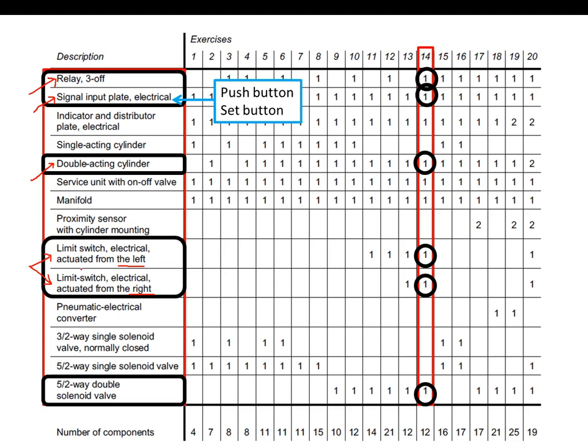We also need to use a 5/2-way directional control valve (DCV). It must be 5/2-way because we are using a double acting cylinder, which can only be controlled by a 5/2-way valve. Bear in mind that it has a double solenoid — not spring return — making it a memory valve.